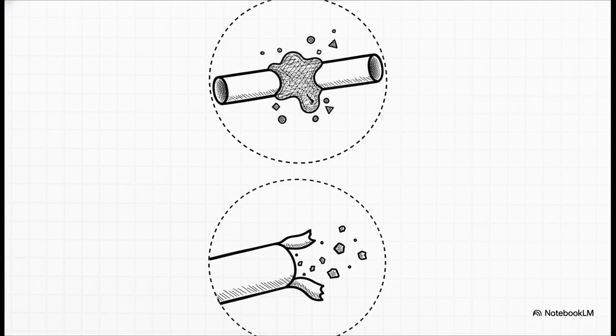And please, don't forget about surface treatments. I'm talking about cyanoacrylate adhesives bonding your joints, or those lubricious coatings on the catheter surface. Think of surface treatments almost like the frosting on a cake, except in this case, that frosting might contain highly reactive, unreacted monomers from an incomplete adhesive cure, or it could shed particulates from a coating that delaminates and wears down over time.